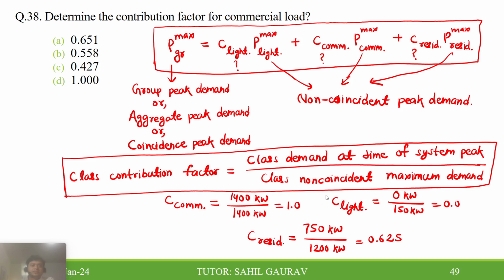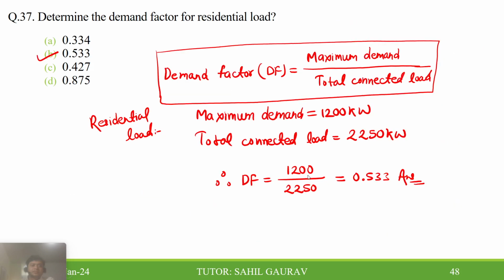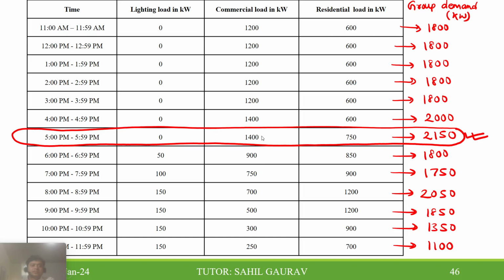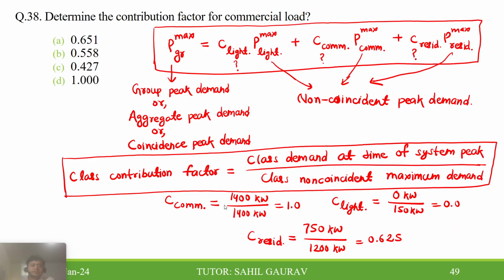So we have found this system peak. Now we have to find the contribution factor for commercial load. You have to note down this class demand at the time of system peak. For commercial load, this value is given as 1400 kilowatt. You have to take this value. We have nothing to do with the group peak demand here. Note down that this 1400 kilowatt is the demand during the group peak demand. So the numerator will be 1400. So I am calculating the contribution factor for commercial load.